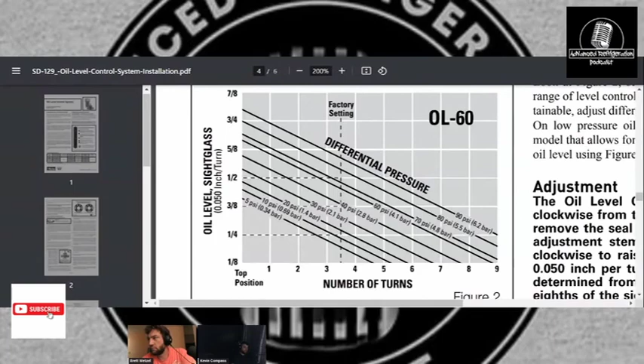So that's why it's incredibly important to make sure this differential pressure is sitting at the proper amount, because say if you take that same compressor with that 20 psi differential and that half glass and you're almost wide open and it gets cranked to say 80 pounds of differential, you're going to be almost 3/4 of an inch in the sight glass, almost slapping the crank. So that's why it's super important to make sure that oil differential works properly, whether you have an OCV or you have an oil differential valve. Making sure that is set properly is key to making these floats work properly.